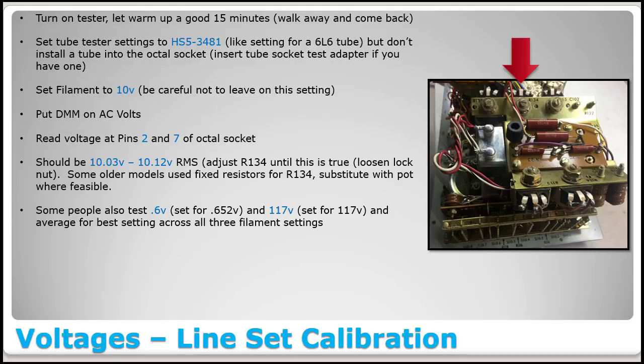So if you can get the 10 volt setting right on this, the other two ends will kind of follow suit. Put your digital multimeter on AC volts, connect across pins 2 and 7. If you're using the socket adapter, that's easy. You clip the two leads on there. If not, you're going to have to use some kind of little leads that have protruding metal ends that you can stick down inside the pin sockets, and you're going to have to hold those in there while you adjust things, which is a little bit of a pain. What you should be looking for is 10.03 volts to 10.12 volts RMS across pins 2 and 7, and make sure that's on AC volts when you do that. And you're going to adjust R134 until this is true.